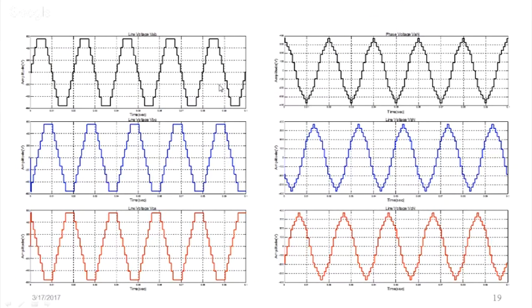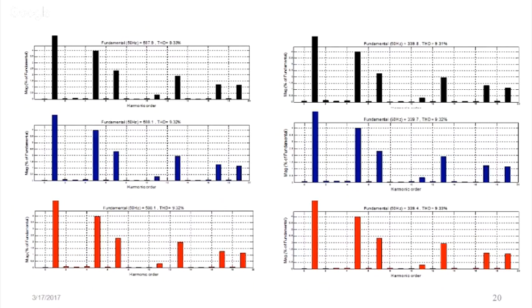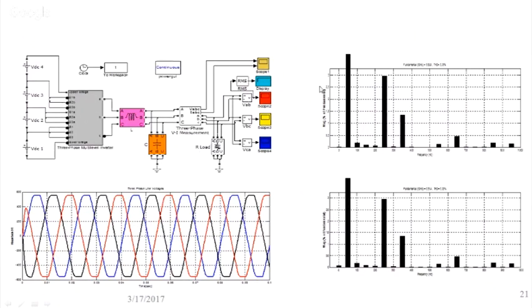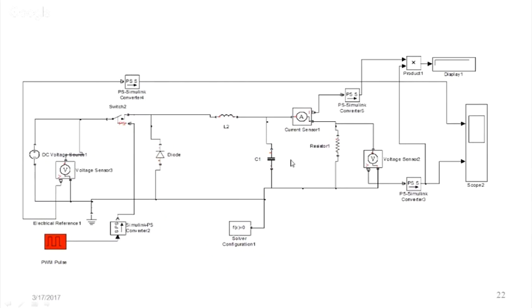The simulated THD without filter is approximately 9%. With an LC filter it reduces to 3%. For different values of alpha1 and alpha2, the THD changes accordingly. The filter effectively eliminates higher-order harmonics and is used when those harmonics need to be suppressed, otherwise the firing angles can be optimized alone.